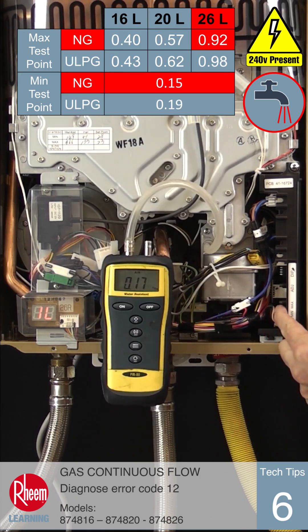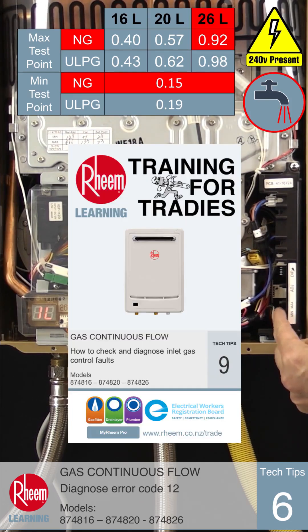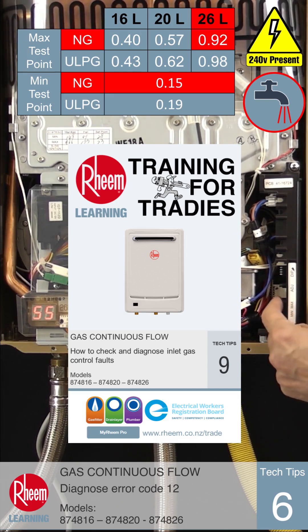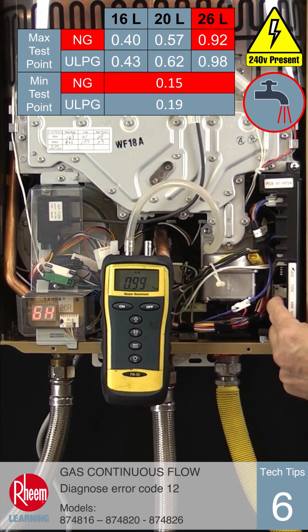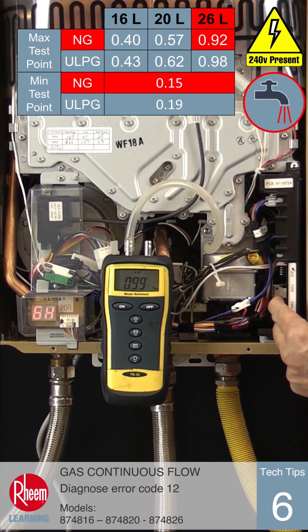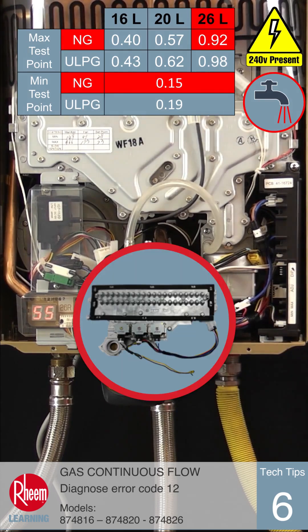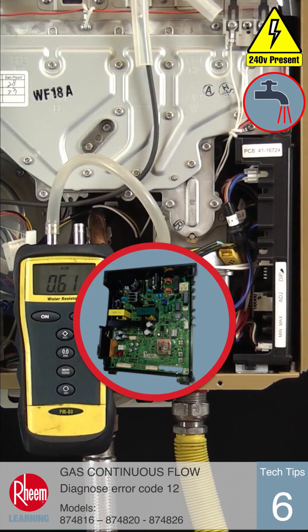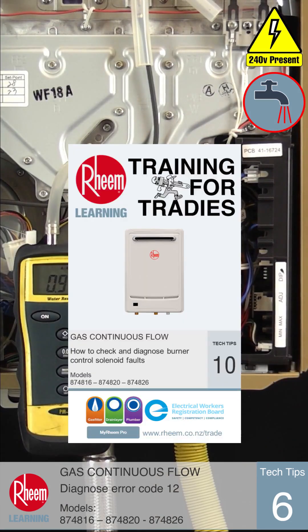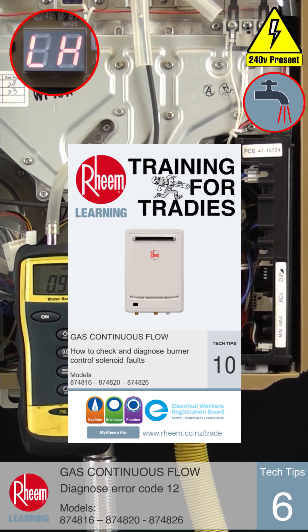If the burner pressure is incorrect and adjustment is not possible, follow details in Tech Tips number 9 which covers how to diagnose inlet gas control valve faults. If the burner test point pressure is correct during the ignition sequence, there may be a problem with the burner solenoid valves 1, 2 or 3 or the PCB. Tech Tips number 10 covers how to diagnose these faults.